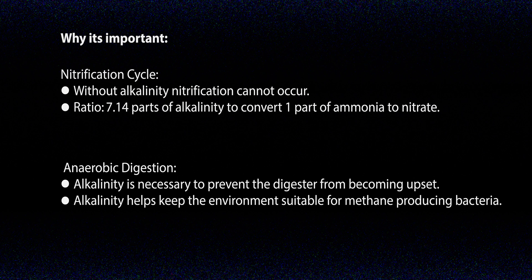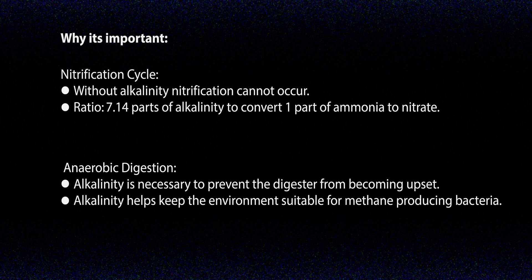Two important instances of why alkalinity matters in wastewater operations: first, the nitrification cycle relies on alkalinity to function properly — without sufficient alkalinity, ammonia cannot be effectively converted to nitrates. A key fact to remember for your exam is that it takes 7.14 parts of alkalinity to convert one part of ammonia into nitrate. Second, in anaerobic digesters, a delicate balance exists between acid-producing and methane-producing bacteria. If acid-forming bacteria lower the pH too much, methane-producing bacteria become inhibited, reducing gas production. Maintaining proper alkalinity helps buffer the system and ensures stable methane generation.